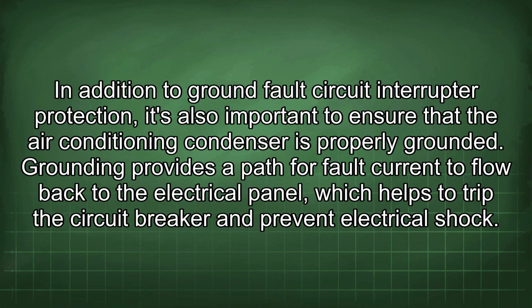In addition to ground fault circuit interrupter protection, it's also important to ensure that the air conditioning condenser is properly grounded. Grounding provides a path for fault current to flow back to the electrical panel, which helps to trip the circuit breaker and prevent electrical shock.